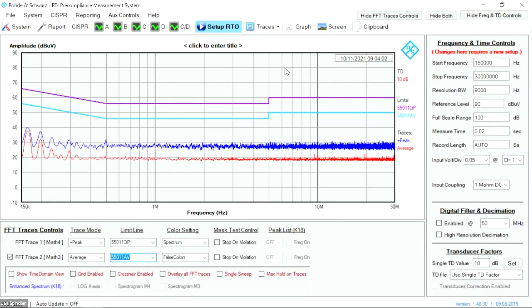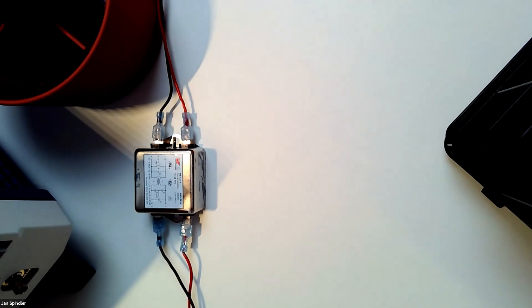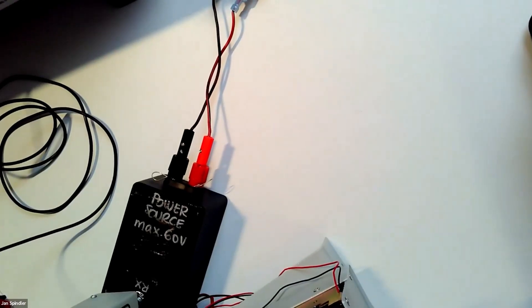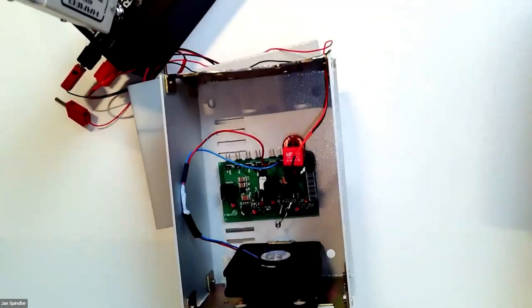Let me switch off my product. My product is off now, and you can see the noise is still here — this noise is coming from my power supply. So if you are trying to test your product with a switching-mode power supply in your laboratory, take care, because the power supply can have a lot of noise. This is where a large, heavy linear power supply is so useful in a laboratory. In my setup, I am using a filter between my power supply and my line impedance stabilization network.